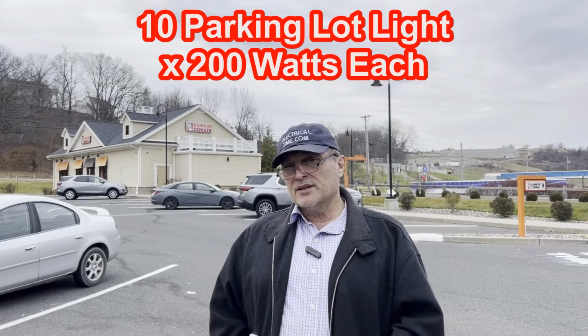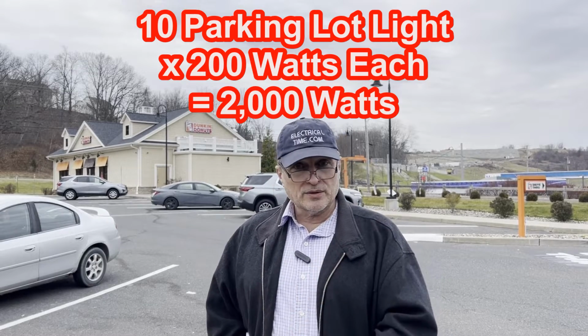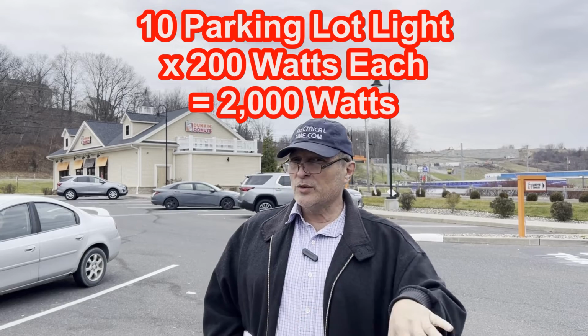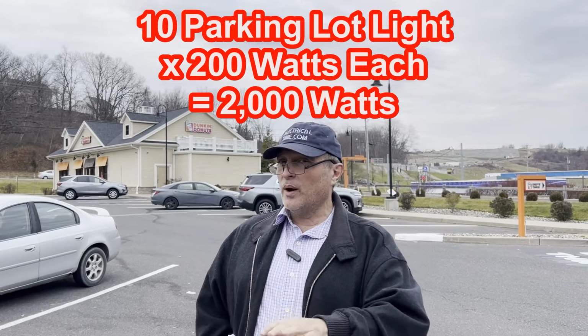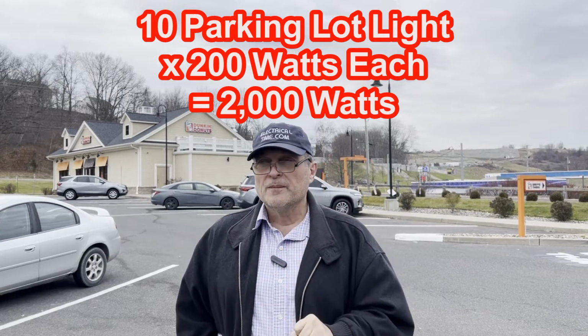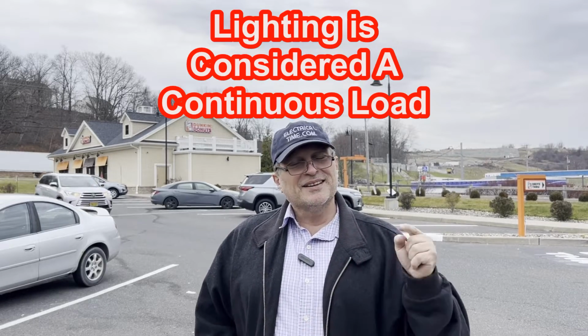So we got 10 lights at 200 watts. That's 2,000 watts. You notice I'm not talking about voltage yet. I'm just talking about watts. Okay, really important. So now, lighting is something special. And Ning, what do you think that special thing is about lighting? Continuous load. It's a continuous load.